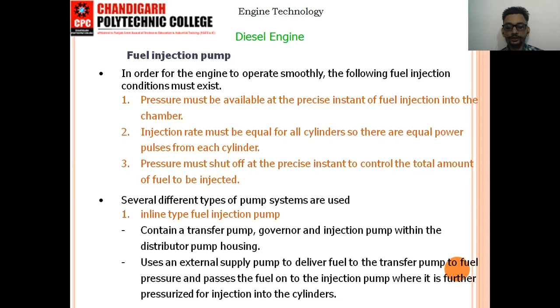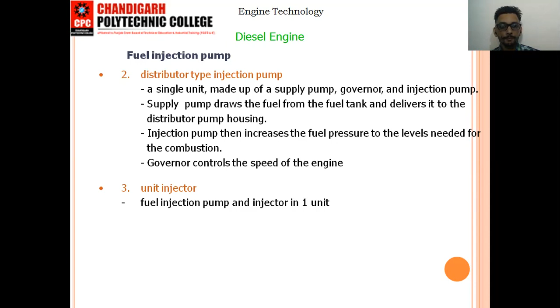Second type is the distributor type injection pump, which is also one of the four types we discussed in the previous slides. It is a single unit made up of a supply pump, governor and injection pump. The supply pump draws the fuel from the fuel tank and delivers it to the distributor pump housing. The injection pump then increases the fuel pressure to the levels needed for combustion. The governor controls the speed of the engine. The main function of the governor is to control the speed of the engine and to supply the fuel when the engine is required to run on the road. Third is the unit injector. Fuel injection pump and injector in one unit.